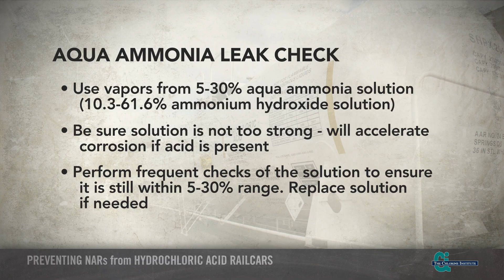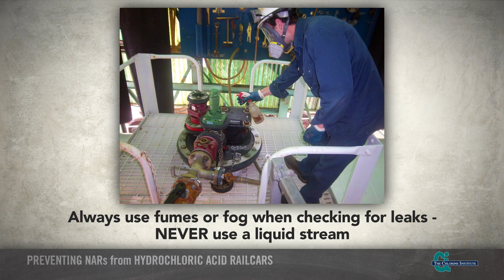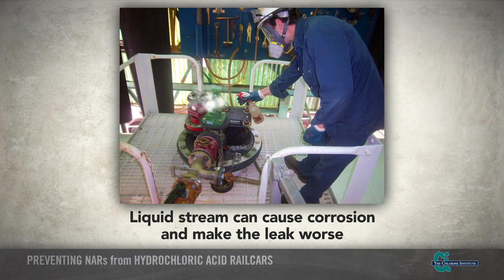A common dispersal method for the aqua ammonia solution is to use a squeeze bottle with an internal tube that only extends into the vapor space of the bottle. If the bottle you have has an internal tube that extends into the liquid space, it is suggested to either remove the tube or cut the tube to a length that extends only into the vapor space. Many different bottle styles are acceptable. It is very important not to use a liquid stream when performing the aqua ammonia leak check, because if a leak is present, the liquid can cause corrosion and make the leak worse.